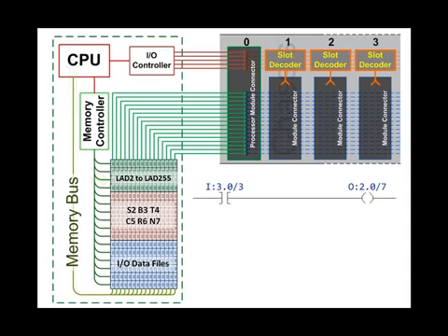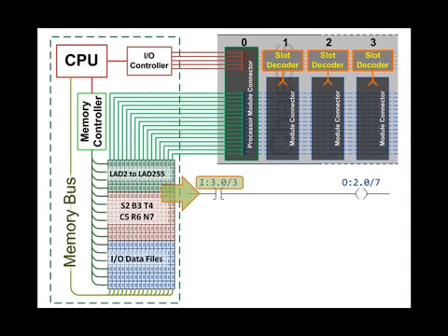First, by reading the state of the memory location that the first instruction is addressing. Then the processor solves the first instruction against the state of the memory location that the instruction was addressing. The instruction, an XIC, which stands for examine if closed instruction, is more properly referred to as a true if on instruction. This instruction is true if I:3.0/3 is on.